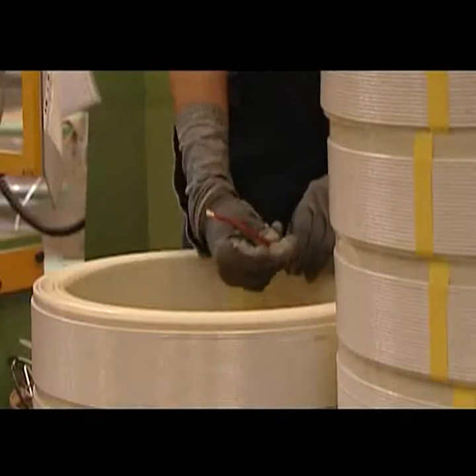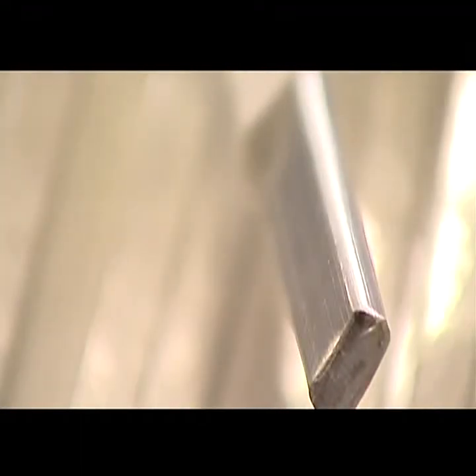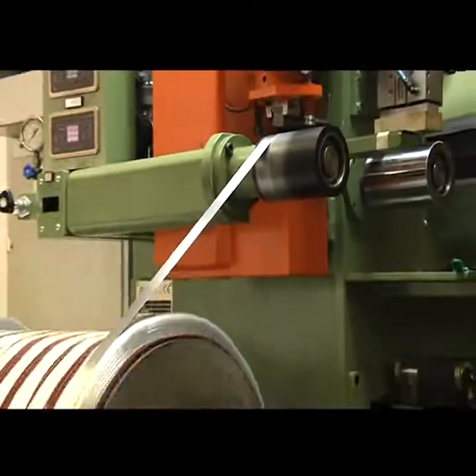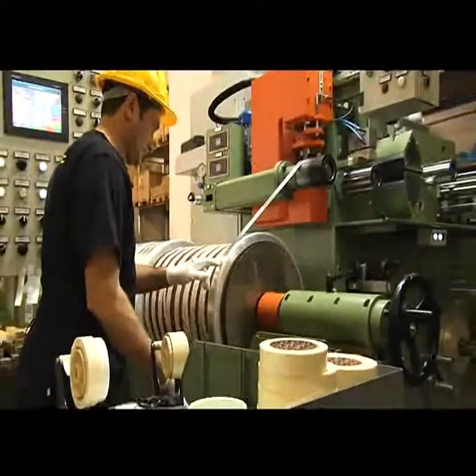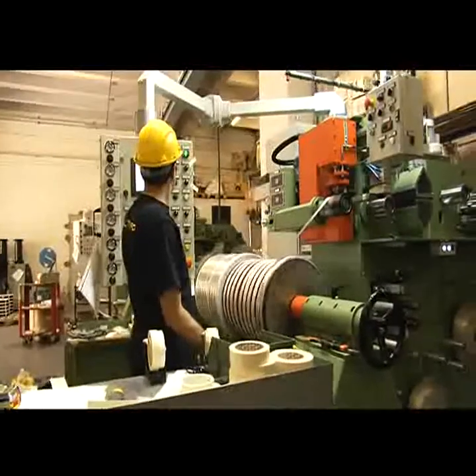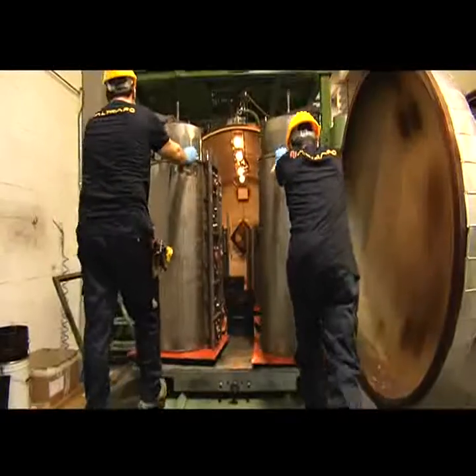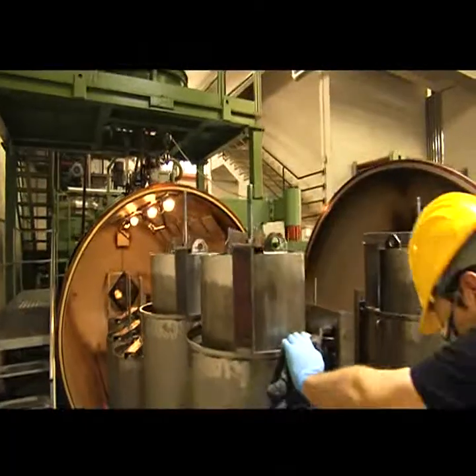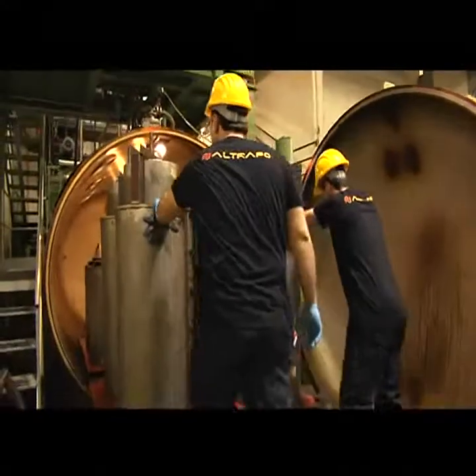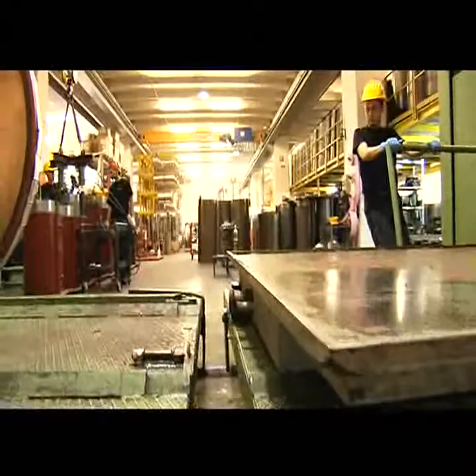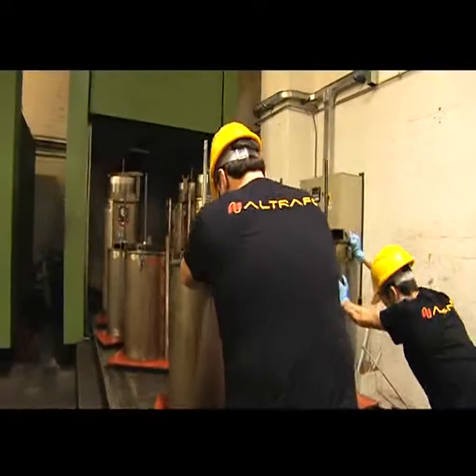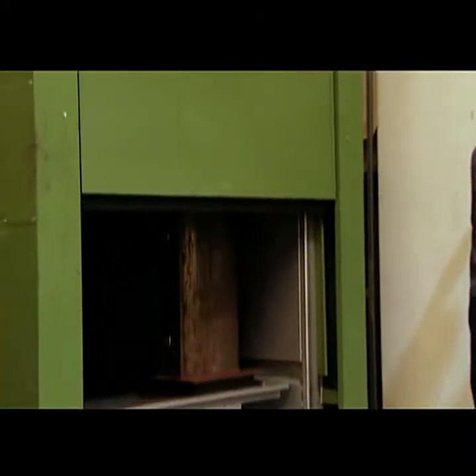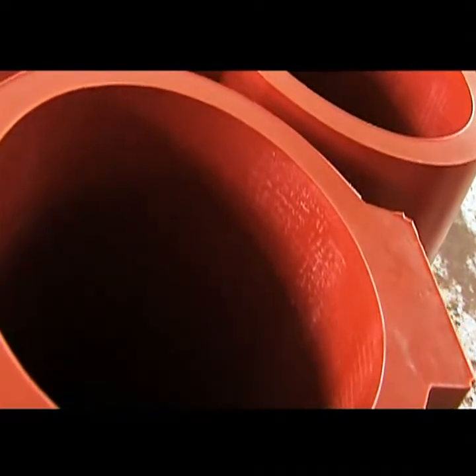Medium voltage windings are realized in wire, strap or foil of aluminium or copper, and they are class F insulated. Coils are wound by means of a semi-automatic winding machine. After a suitable thermal desiccation pre-treatment, they are set in metallic molds and cast in a compound based on epoxy resin and aluminium. The casting takes place in a vacuum tank. The process is completed when, in the furnace, the glassy transition is reached, and this gives to medium voltage coils their typical monolithic consistency.